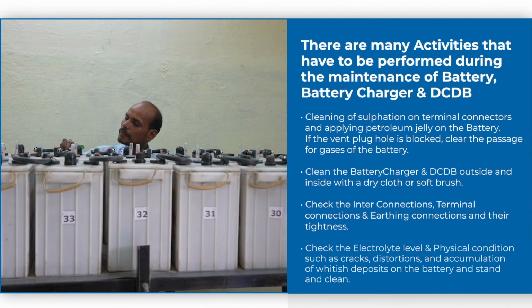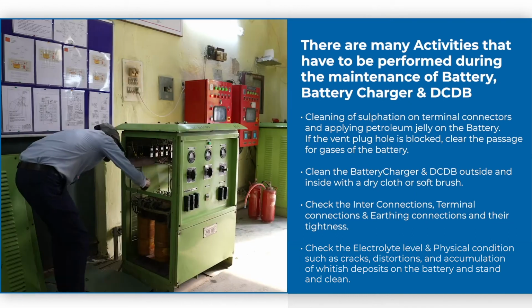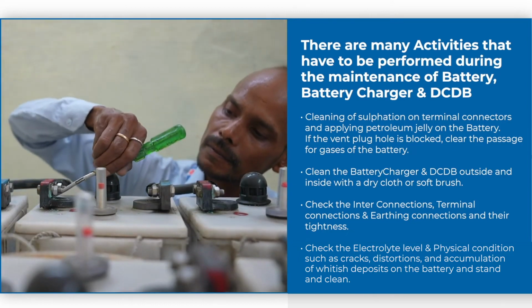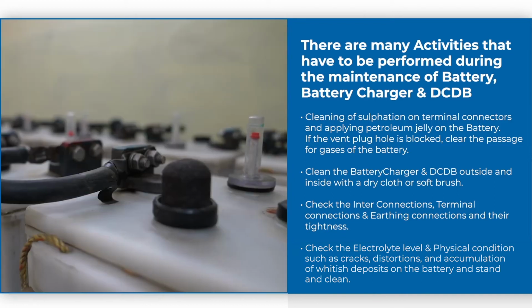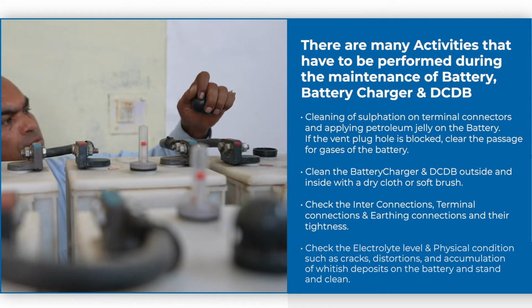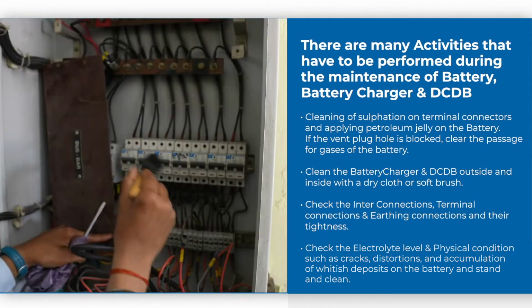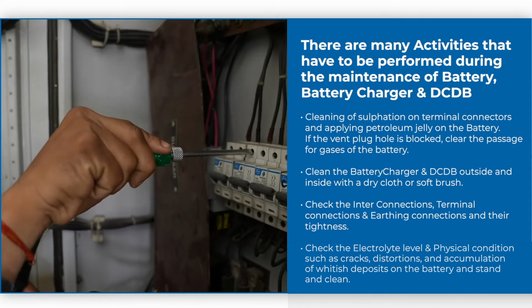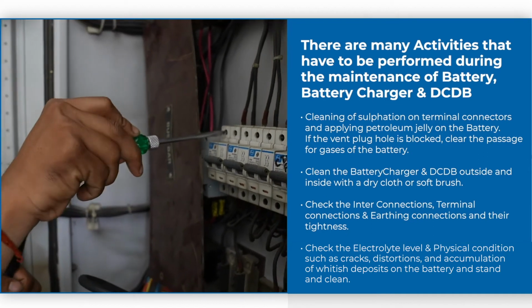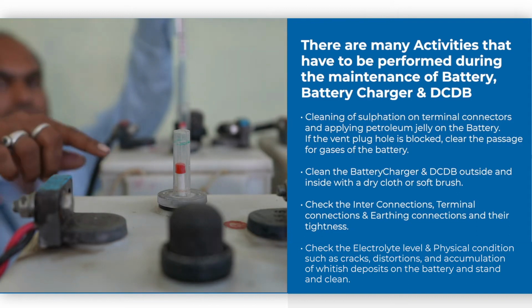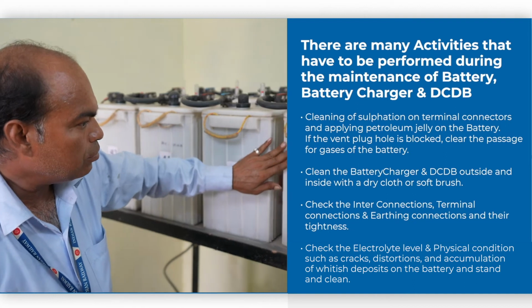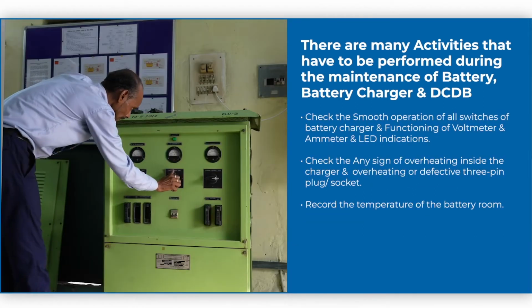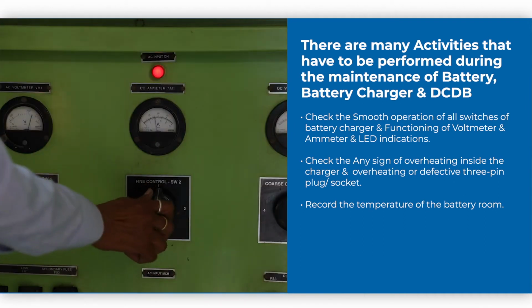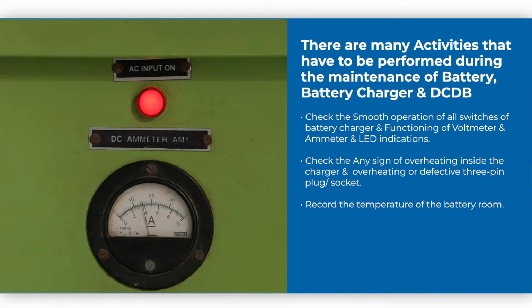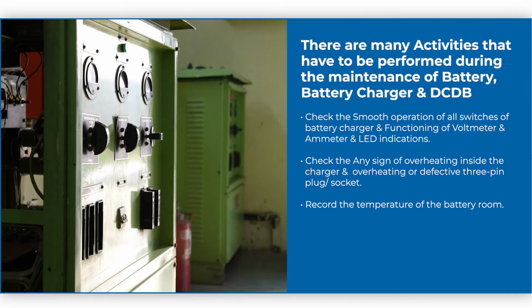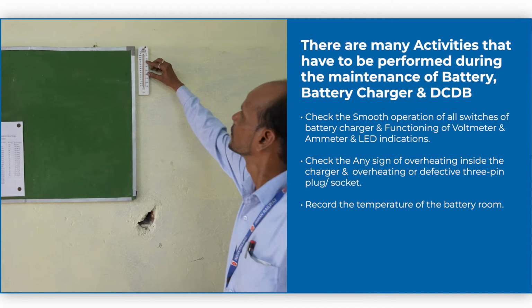There are many activities that have to be performed during the maintenance of battery charger and DCDB. Clean sulfation on terminal connectors and apply petroleum jelly on the battery. If the vent plug hole is blocked, clear the passage for gases of the battery. Clean the charger and DCDB outside and inside with a dry cloth or soft brush. Check the interconnections, terminal connections and earthing connections and their tightness. Check the electrolyte level and physical conditions such as cracks, distortions, and accumulation of whitish deposits on the batteries and stand, and clean. Check the smooth operation of all switches of battery charger and functioning of voltmeter, ammeter and LED indication. Check any sign of overheating inside the charger and overheating or defective 3-pin plug socket. Record the temperature of the battery room.